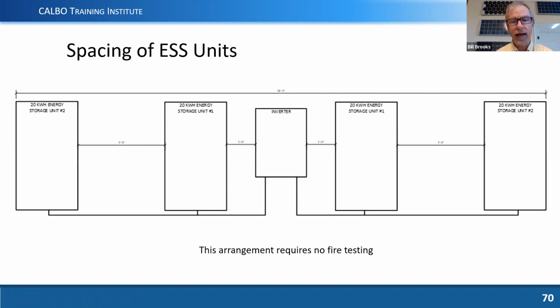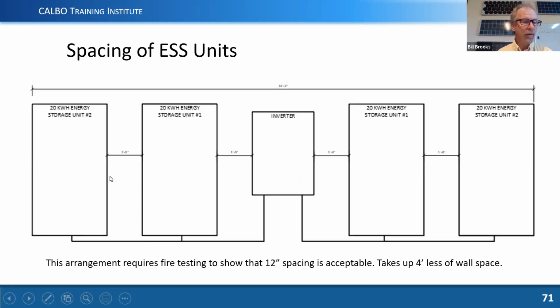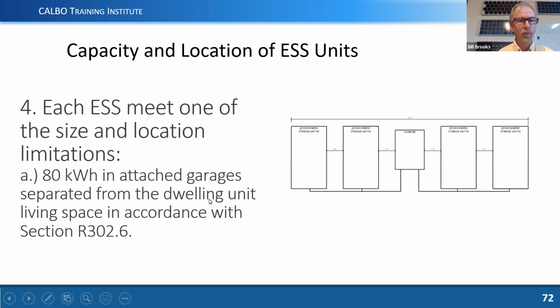I can tell you for a fact that there are very, very few residential garages that have 18 uninterrupted feet of wall space. Now, if you were lucky and there happened to be a window in between these, that would just be straight up luck. But that's an enormous amount of wall space that would be required if you're going to have no fire testing. That's why almost every ESS company is going to do these large-scale fire tests, whether it says they have to be 6 inches apart or a foot apart or whatever they say as a result of that testing. That's going to dramatically reduce the wall spacing. In this particular case, it went from 18 feet to 14 feet, but it might even be quite a bit less than that. So just be aware that there are big differences when we get into that energy storage testing, the fire testing that's required, large-scale fire testing.